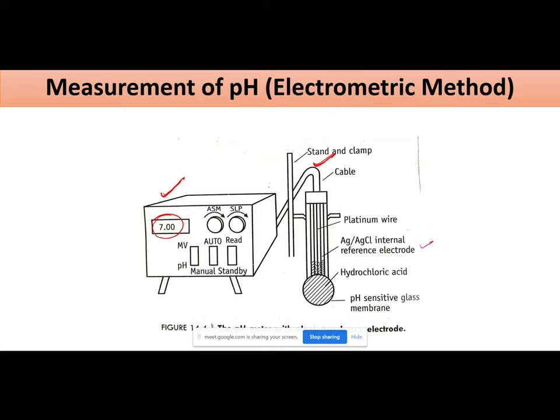In this glass electrode, you basically have a silver-silver chloride internal reference electrode filled inside your glass bulb. That glass bulb is filled with hydrochloric acid. The hydrochloric acid pH is fixed because it is sealed in this electrode and not getting contaminated — it remains fixed during usage. Then you have a platinum wire in between. This entire assembly is called a glass electrode.